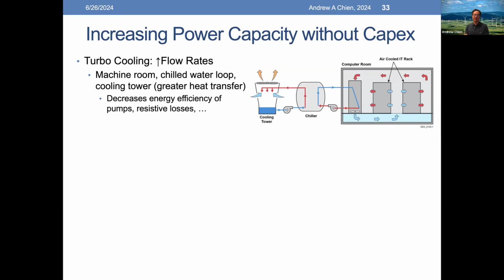At a fundamental scientific level, you can increase power capacity without increasing CapEx by trading some of this energy efficiency. So for example, if we have a machine room, it'll have a chilled water loop, it'll have a cooling tower, and so on. What we can do to increase the cooling capacity is increase the flow rates, at all of these levels, in this loop, and in the room, and so on. Now, the normal reason why you wouldn't do this is it decreases energy efficiency. It decreases the efficiency of the pumps. There's resistive losses. They can even grow non-linearly. We've studied all of these things, but it's still possible, at some cost in energy efficiency, to drive this capacity up.